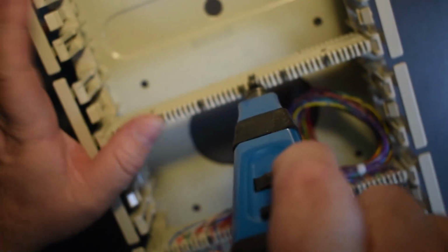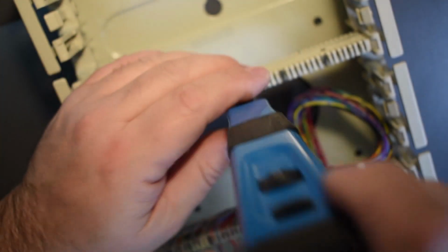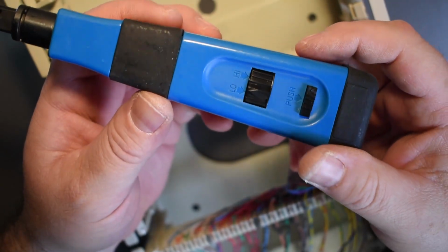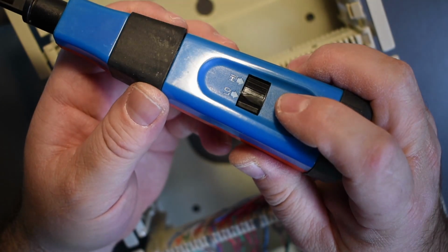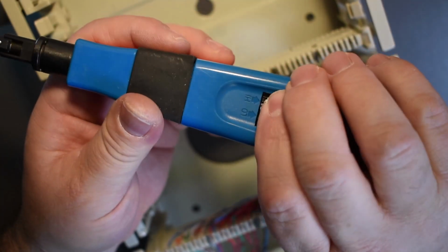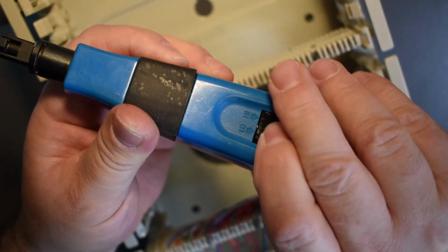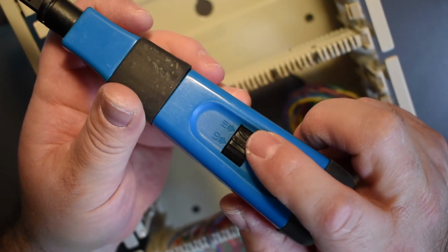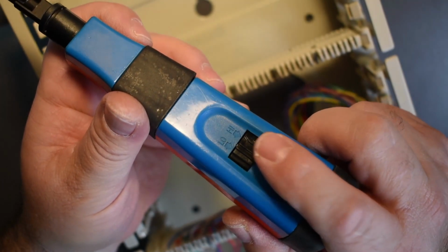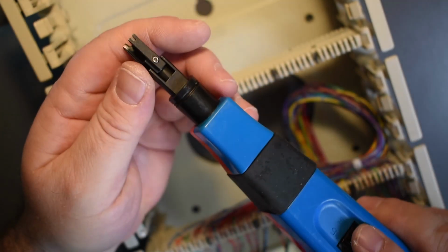So once you put that, it just does that. It just has an impact, spring-loaded impact action. And over here, you see there's a high and low impact. This one is selected to low impact. So I'm just going to twist that around. See that? Twist that around. It just takes a little bit of strength here. So that one's going to be the high impact tool. We want a high impact on this BIX for sure.